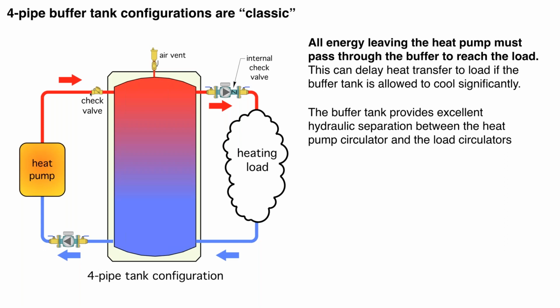And we've seen this happen over the years. Again, this is really independent of what the heat source is, but when you're designing hydronic systems around any heat source, it is always beneficial to have hydraulic separation between the circulators. The ultimate concept of hydraulic separation is each circulator thinks it's the only circulator in the system. And when it turns on, it provides a certain flow rate and a certain differential pressure. And that flow and differential pressure are not affected if another circulator happens to turn on or off in the system.